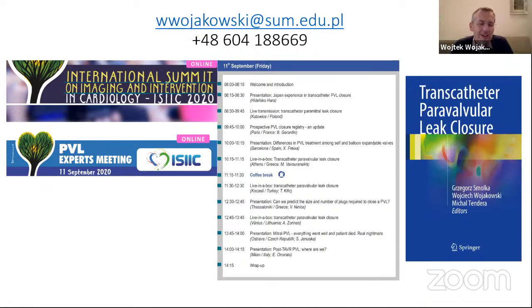Yeah. And then in such a way you can also have 3 sheaths in the large guide. So then you can deploy 2, 3 AVPs simultaneously, and you open each one at the same time, but you use 3 or 2 different coronary guide catheters. Yeah. If you want to use 3 or 4 AVPs at the same time, you can also use a large vascular sheath like a Cook sheath, 9 French, for example, or 8 French, depending on the size of the defect, and you can do it using the 1 sheath.